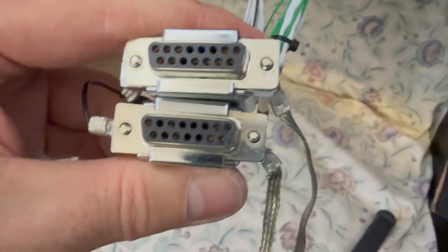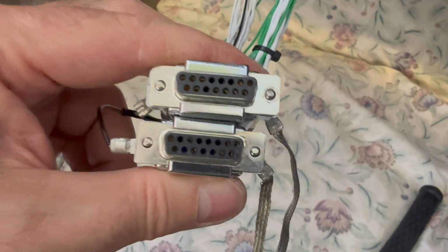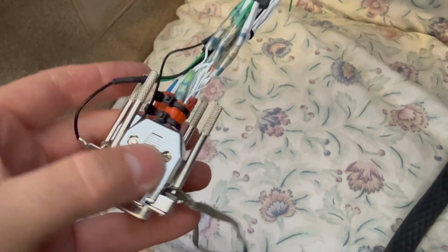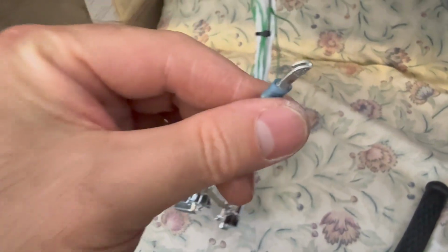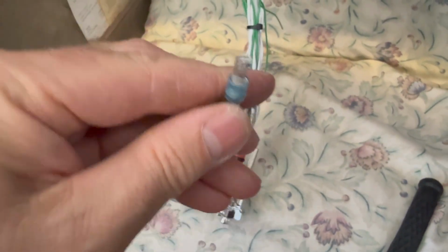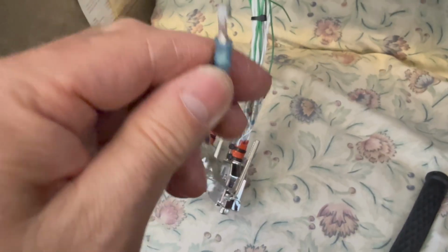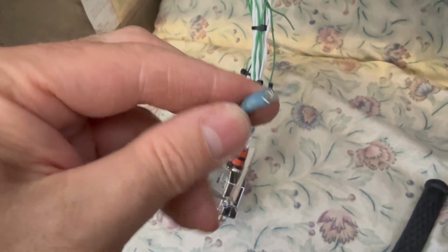I also stack them up to make sure that both the D-sub connectors are going in the right direction. I got both my grounds and bonding strap on the correct side. What I did, I jumped these two bonding straps to a single point knife disconnect, and then I've just got that hardwired to the panel, so it makes for easy, quick disconnects if I need to do service work like this. So yeah, these things are pretty much ready to go.